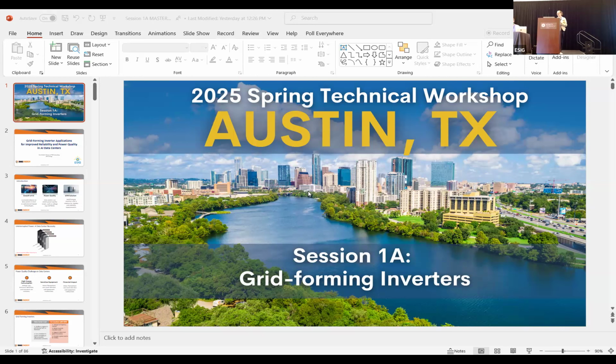And you can see that happened at 3. So as soon as the grid hit 59.4, the facility injected an additional power step. And then from there, the frequency could start recovering. So we're very proud of this facility and the role that it's playing in the Oahu grid.